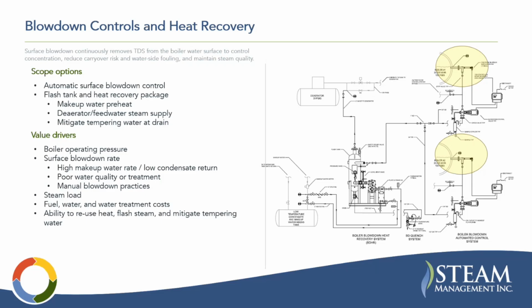But the value drivers for this scope are a higher operating pressure of the boiler. That means the blowdown stream is going to have more energy in it. Then the rate of the blowdown, which is driven by your makeup water rate. As I mentioned, makeup water introduces dissolved solids that requires more blowdown. If that makeup water is poorer quality and it's going to have more impurities in it, then you're going to increase your blowdown requirement. And then, as I mentioned, manual blowdown practices are going to increase the amount of blowdown you have.